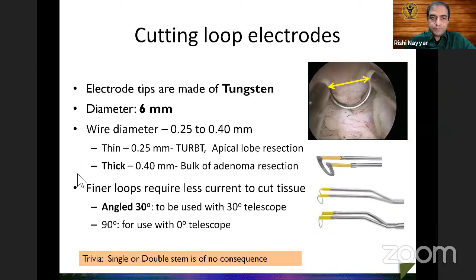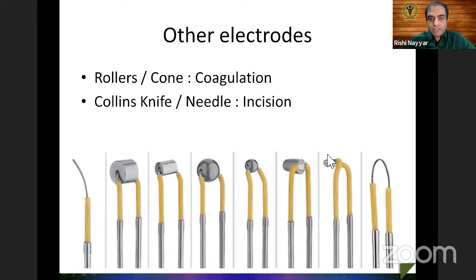And the loops are available in a thick loop or a thin loop, and even angled or straight 90-degree loops are available, each with its own benefits. For the prostate, generally we prefer the thick loop. It uses higher current, but at the same time also produces more vaporization, and therefore resection may actually be faster with the thicker loop. Other kinds of electrodes are available, which one should know just in case there is more bleeding. One may need to use a coagulation electrode like a roller or a cone ball, and sometimes if the prostate is very small or fibrotic, one may need to do only incision, in which case a Collins knife or a needle electrode can be used.